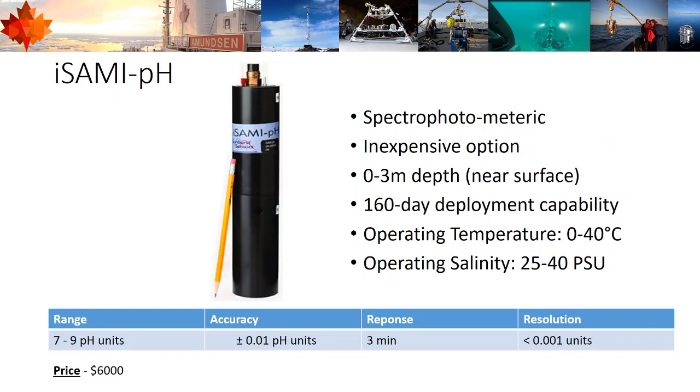The ISAMI pH is based on the same technology as the SAMI pH, using that spectrophotometric colorimetric reagent method, but it's exclusively meant for surface applications. So this is your 0 to 3 meter depths, very close to the surface, and it's very inexpensive.